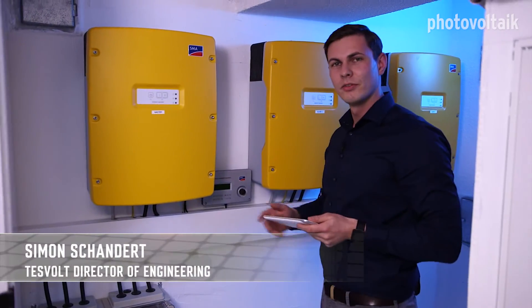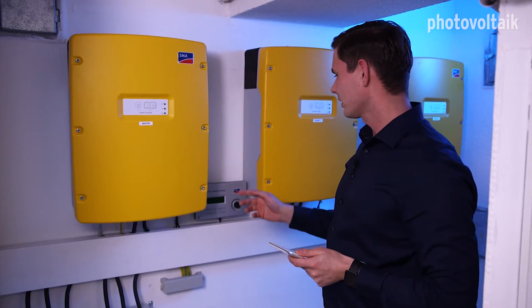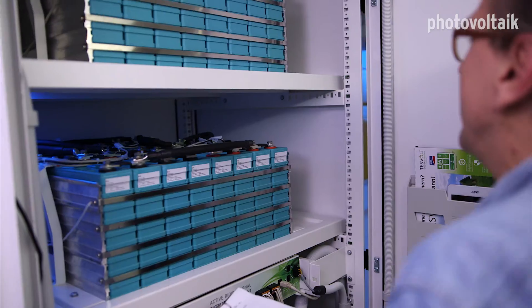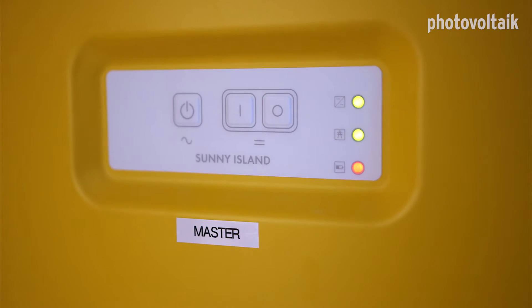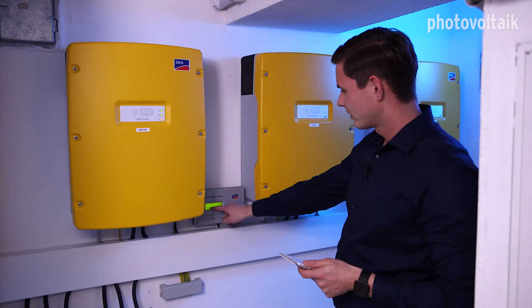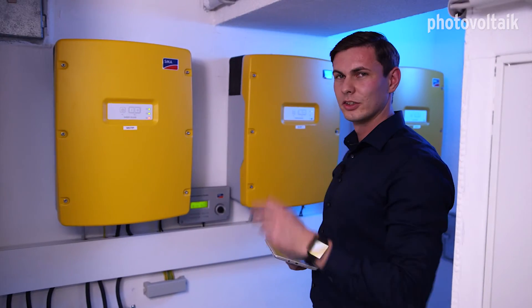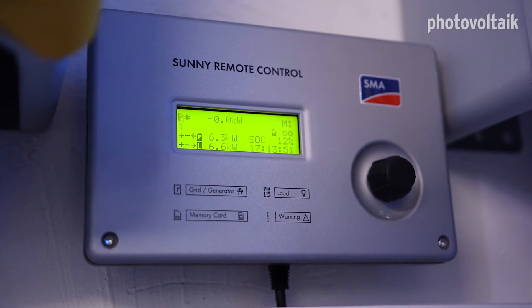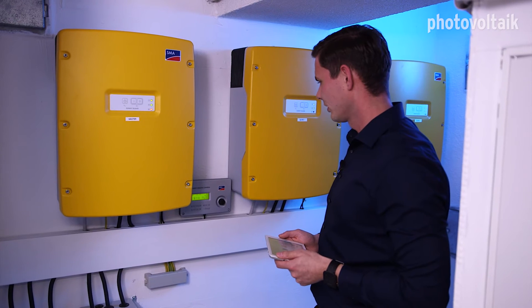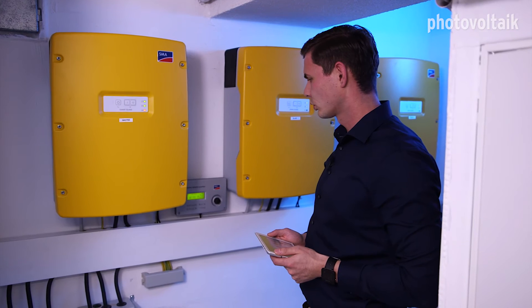The only remaining task is the commissioning of the system. This is the charge controller, which charges and discharges the batteries. Before commissioning, the batteries are switched on and the charge controller starts to work. A rated power of 9.4 kilowatts is being fed into the house's electrical system. The battery charge level is now at 12%, and at the moment there's no energy being taken from the public electricity grid.